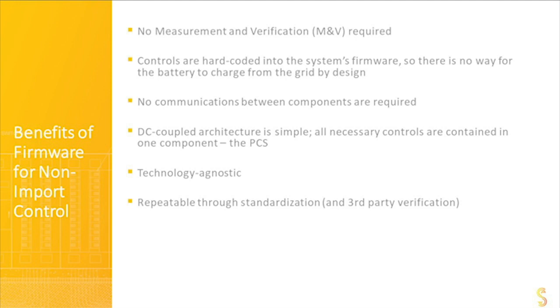And as I mentioned earlier, once UL accepts the ratings of the battery from UL 1973 or 9540, some of the tests we just went through won't even need to be done. They will have already been done, and UL can just check their own UL-listed spec sheet that they tested and listed with the battery from an earlier 1973 test, for example.